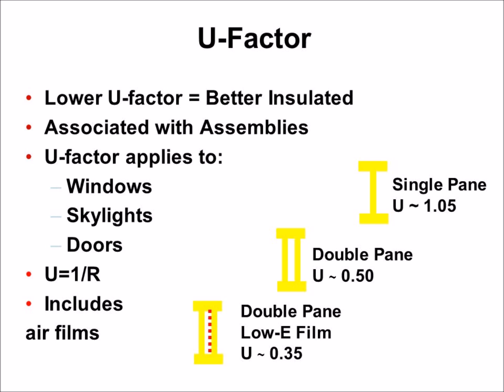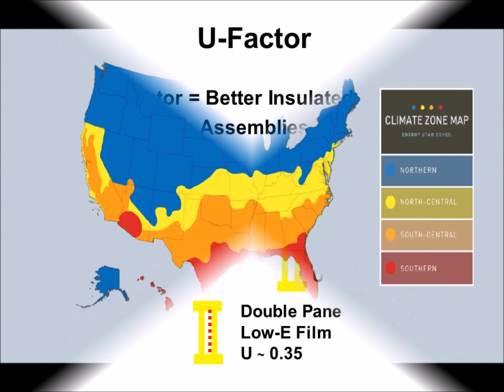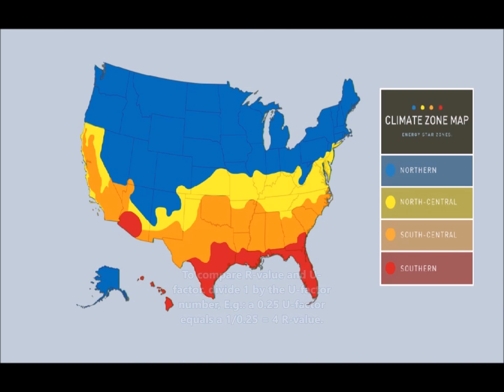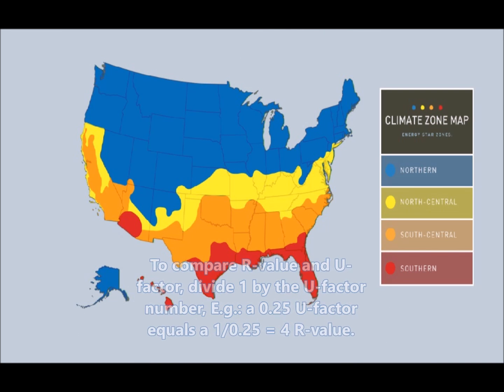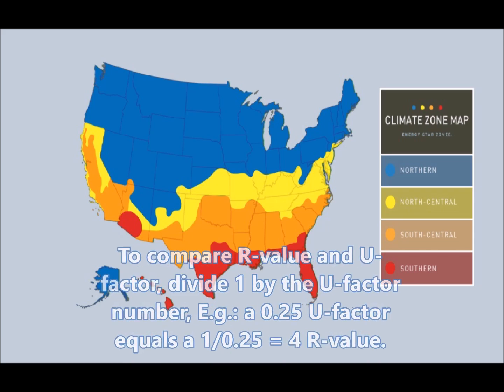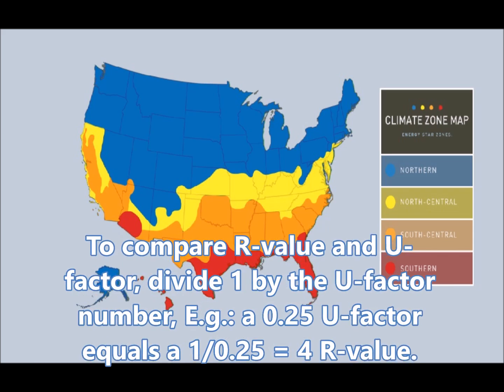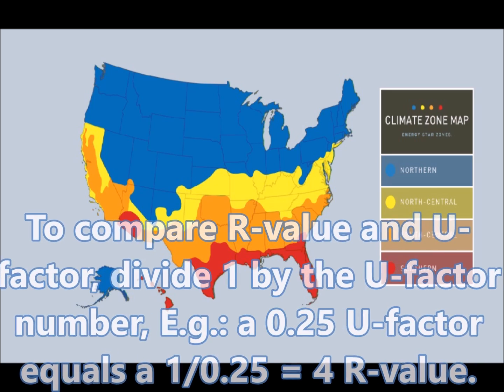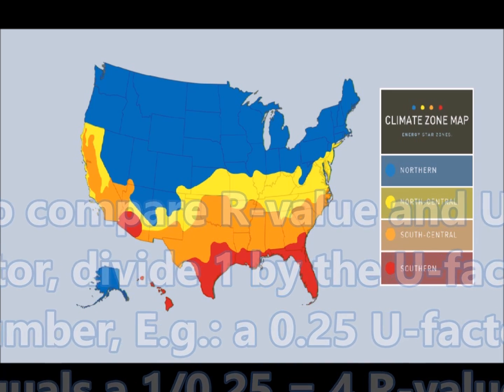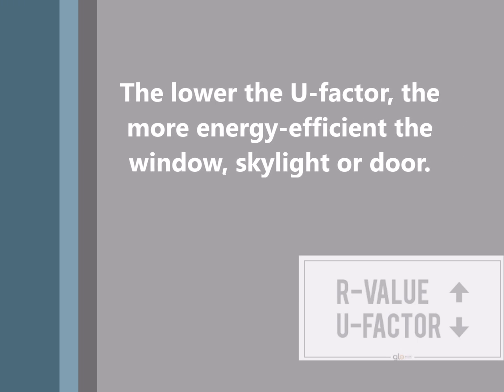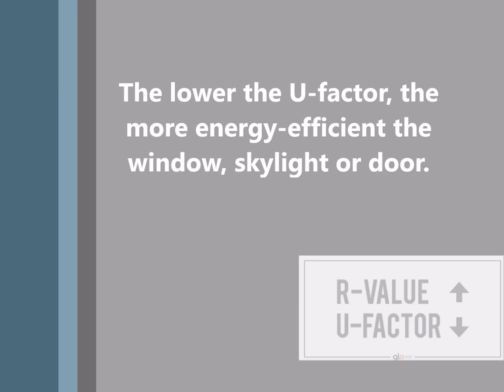To compare R-Value and U-Factor, divide 1 by the U-Factor number. For example, a 0.25 U-Factor equals 1 divided by 0.25, resulting in a 4 R-Value. The rate at which a window, door, or skylight conducts non-solar heat flow is what U-Factor is. So the lower the U-Factor, the more energy efficient the window, door, or skylight is.